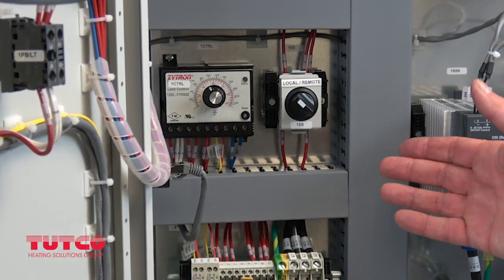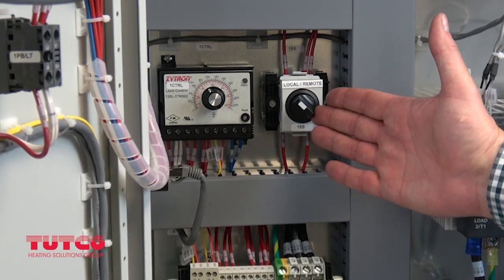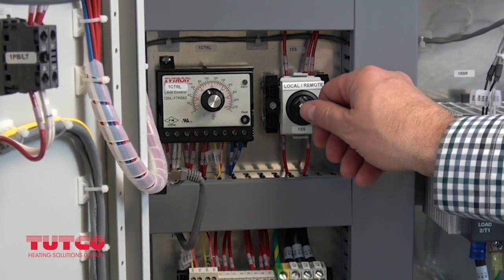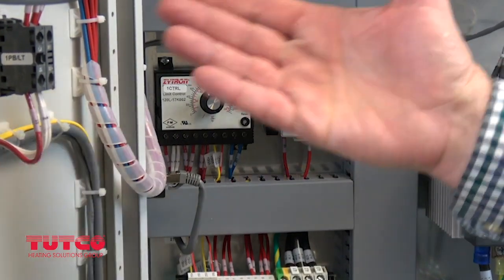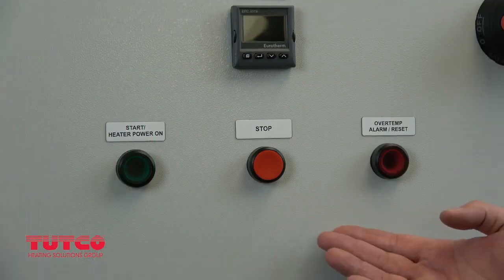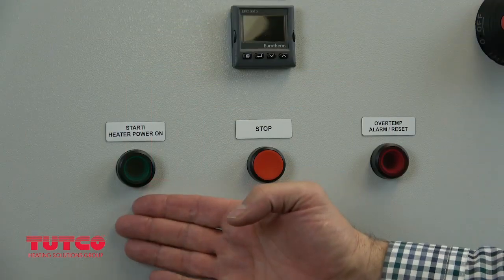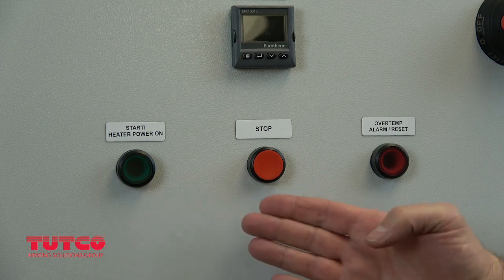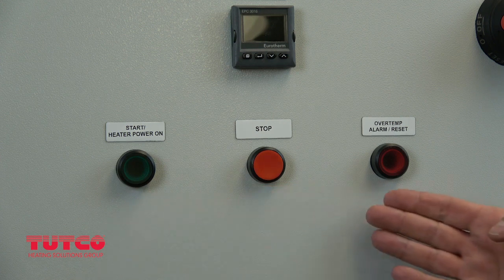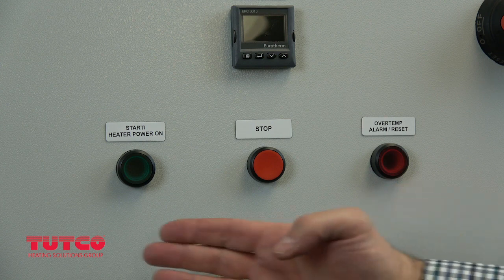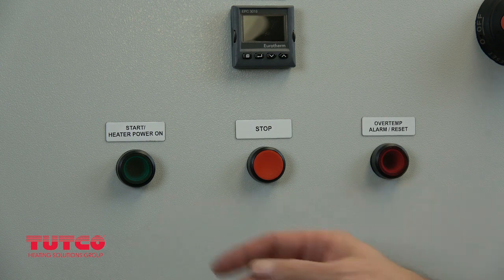Above the thermocouple block, you will see a selector switch that allows you to choose between local and remote control. In local mode, all the temperature controls will come directly from the front of the panel. You will find the controls for start, stop, reset on the front door of the controller. Except for an e-stop, no other remote controls will function while set to local.